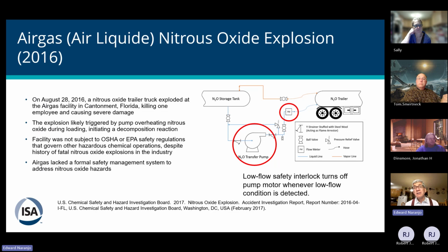It's over 10,000 gallons in one. It's smaller quantities in another. And nitrous oxide doesn't meet that threshold. If you were a refinery, if you were an LNG facility, if you were an LNG terminal, absolutely, you'll have to meet PSM. But these are smaller facilities, and so up till now, these facilities fly under the radar of PSM.